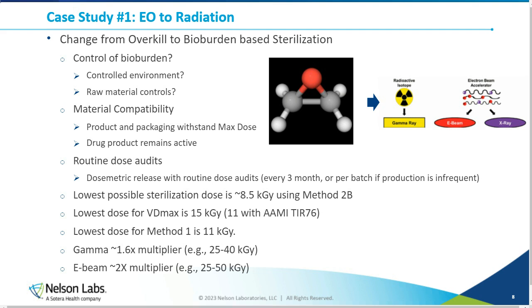So some things to consider with this change is just what some of the limitations with radiation sterilization are. The absolute lowest sterilization dose that we can reasonably achieve when following the ISO standard is around 8.5 kilogray, and that's using a method 2B validation. For those that aren't familiar, a method 2B validation is very involved, it's very expensive, so to get down to that truly low dose is actually quite a process. So if your product isn't able to be materials compatible at a dose past 8.5 kilogray, chances are radiation sterilization isn't going to be a good option for you. That's basically the floor of where we can get down to.